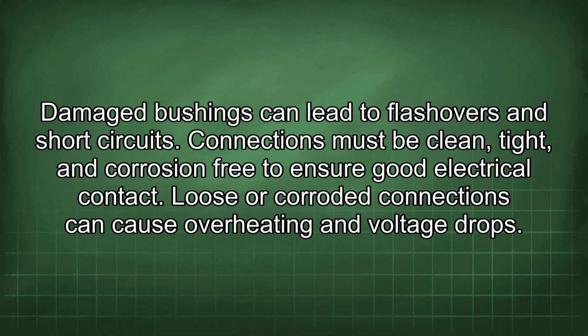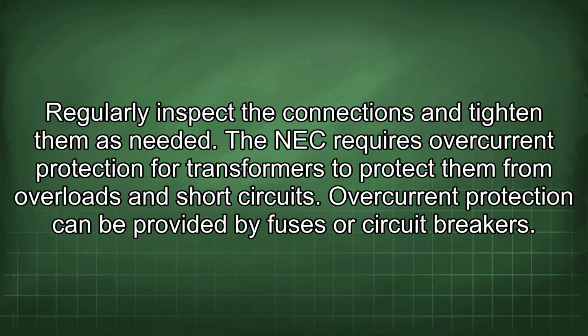Connections must be clean, tight, and corrosion-free to ensure good electrical contact. Loose or corroded connections can cause overheating and voltage drops. Regularly inspect the connections and tighten them as needed.